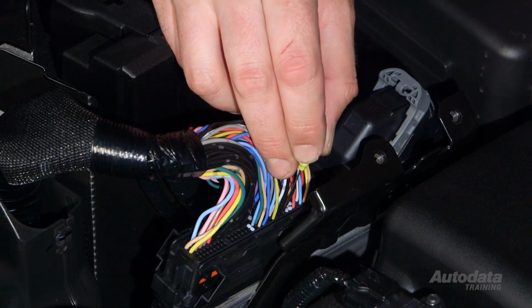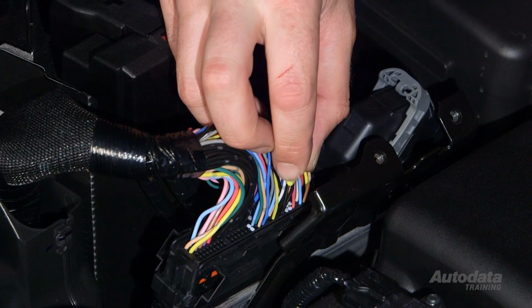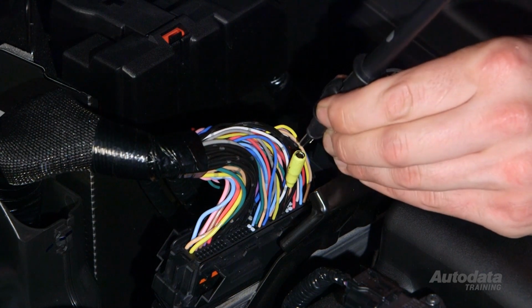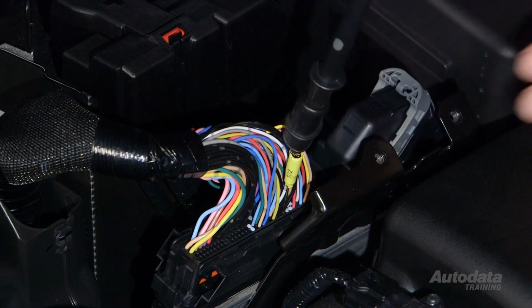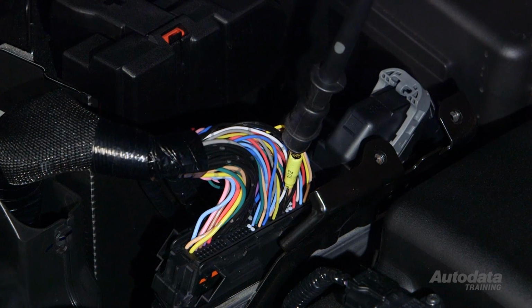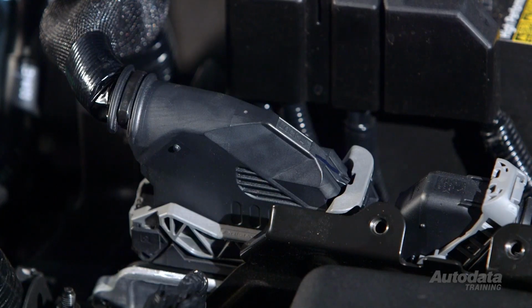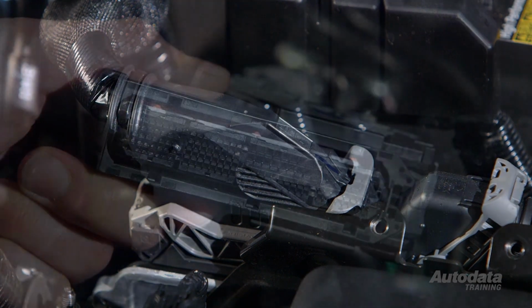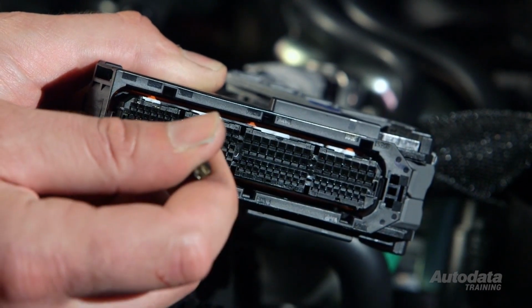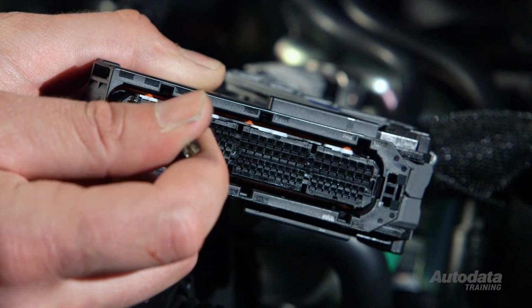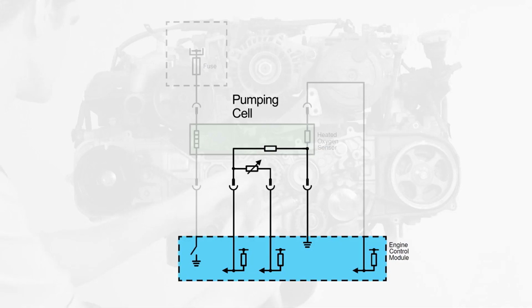If the ground comes from the module, back probe the ECM connector. Again, if there's voltage here, the problem will be in the harness. If there is no voltage, it will be either the ECM connector or the ECM itself. Check the terminal tension and for corrosion on the ECM connector. If the readings all check out, then the fault can only be the ECM.